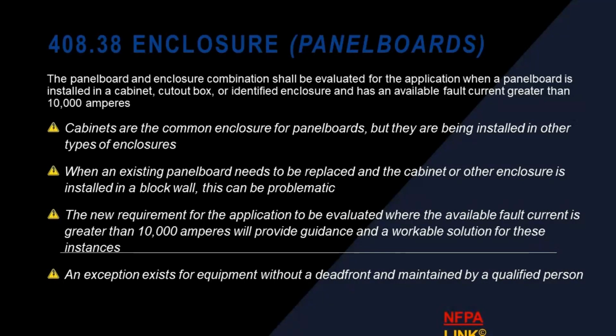The cabinets are the common enclosure for the panel board, but they are being installed in other types of enclosures. When an existing panel board needs to be replaced, and the cabinet or other enclosure is installed in a block wall, this can be problematic. The new requirement for the application will be evaluated where the available fault current is greater than 10K. It will provide guidance and a workable solution for these instances. An exception exists for equipment without a dead front and maintained by a qualified person.